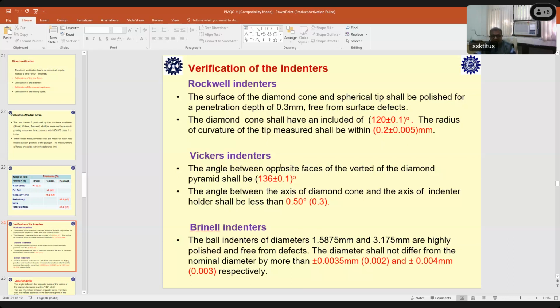So in the case of Vickers, again I told you, we are using a pyramid shape indenter, and this has to be calibrated. All these indenters have to be separately calibrated for their dimensional parameters. The angle is 136 degrees plus minus 0.1, and the angle between the axis of the diamond cone and the axis of the holder shouldn't be more than 0.5 degrees in the case of testing machine indenters, and in the case of calibration machines it should be 0.3.